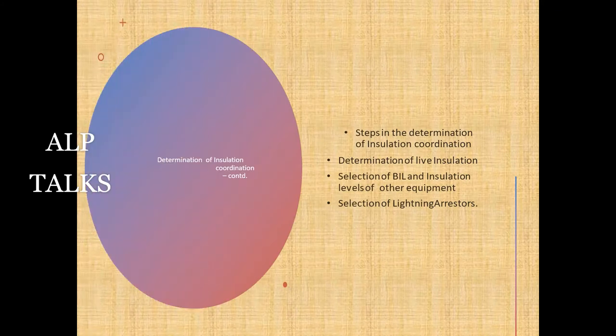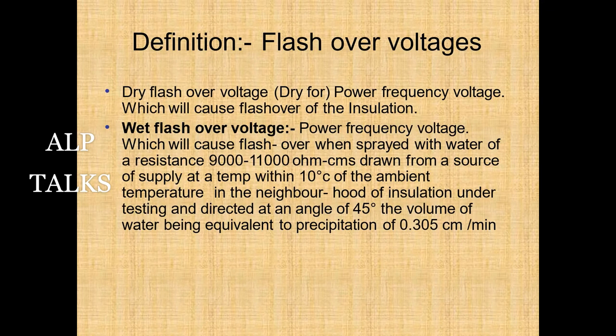The main steps in determination of insulation coordination are: first, determination of line insulation; second, selection of BIL and insulation levels of other equipment; and third, selection of lightning arresters. We will also deal with several important definitions.